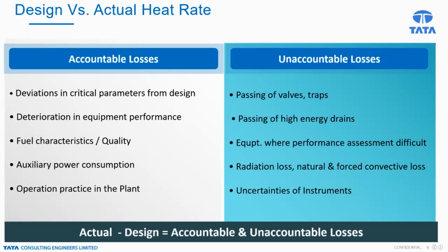That is one. Another is deterioration in equipment performance: boiler, turbine, or any rotating equipment. Because of the continuous operation of the equipment and systems, there will be deterioration in equipment performance, but it can be accounted for because there are various curves available. We can check over a period of time how, for example, the turbine would degrade. There is a degradation factor versus the number of operating hours.